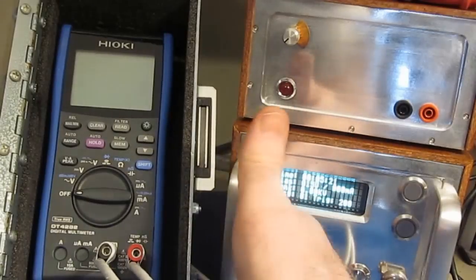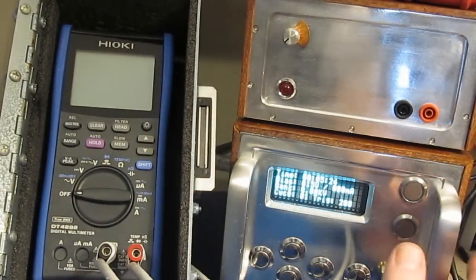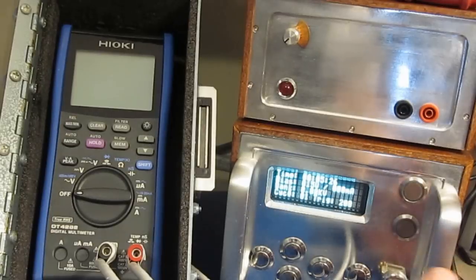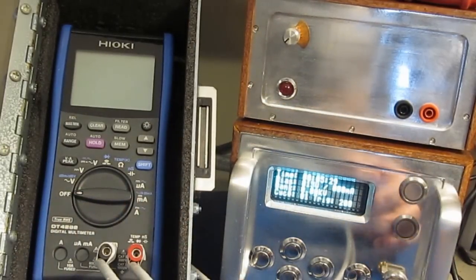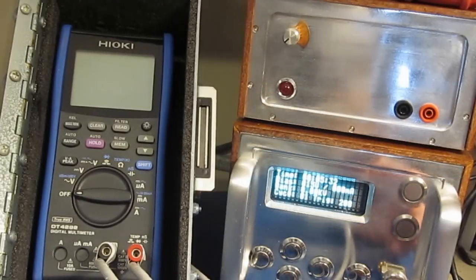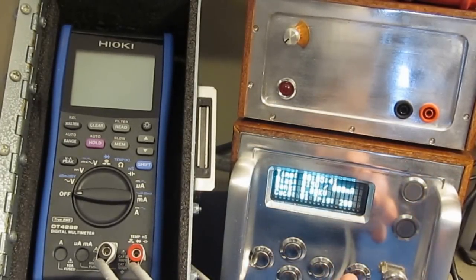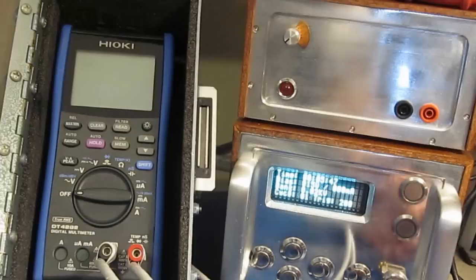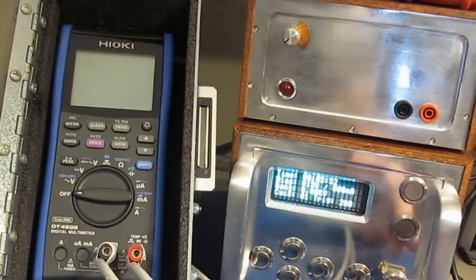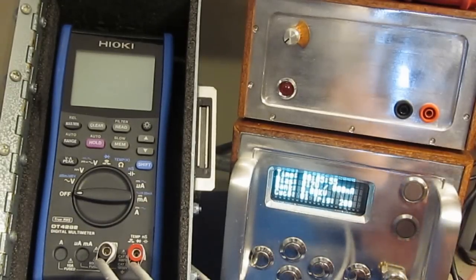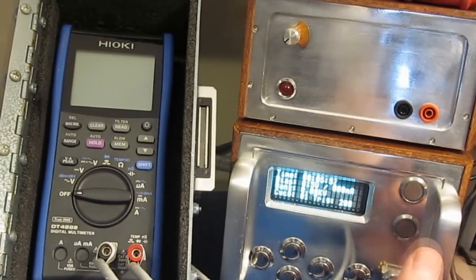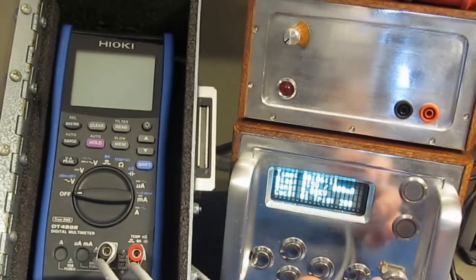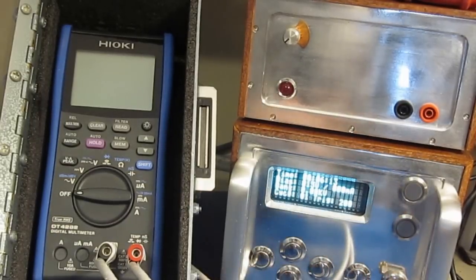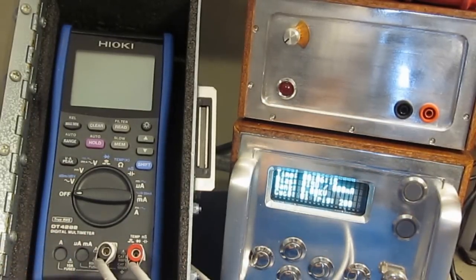The open circuit voltage waveform off of this is actually modeled after the IEC standards that these meters are normally tested to, except for the fact that I've doubled the full width half height. Of course, those IEC standards call for a combo generator. It's called a combo because they're interested in 2 different waveforms. So you have the open circuit voltage as well as the short circuit current. Now, the short circuit current of this does not even come close to matching the IEC standard. But again, I'm not really interested in safety on this channel. What I am interested in is how electrically robust these meters are.